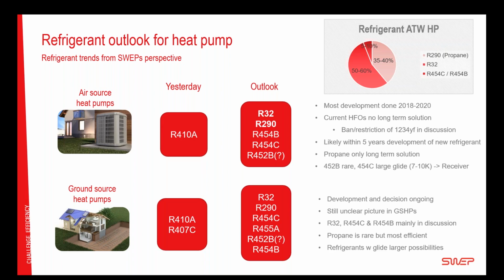Within air-sourced, most of the development has been going on from 2018 to 2020. In the upper right-hand corner of the slide, you see our view of the air-sourced heat pump market, where 50 to 60% today are using R32, 35 to 40% are using propane, and the rest are other refrigerants, with maybe the bigger one being 454C. So that's how it looks on air-to-water heat pumps.